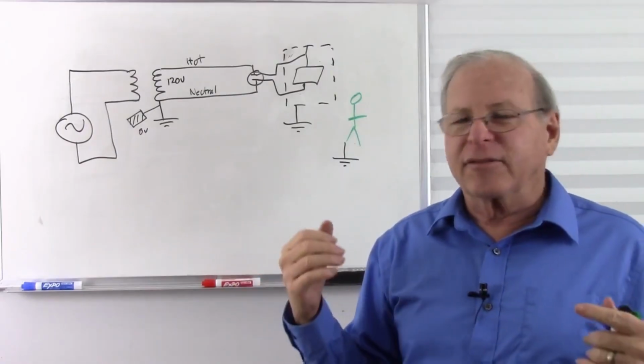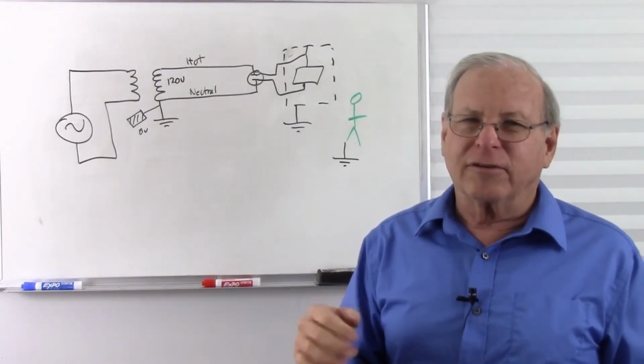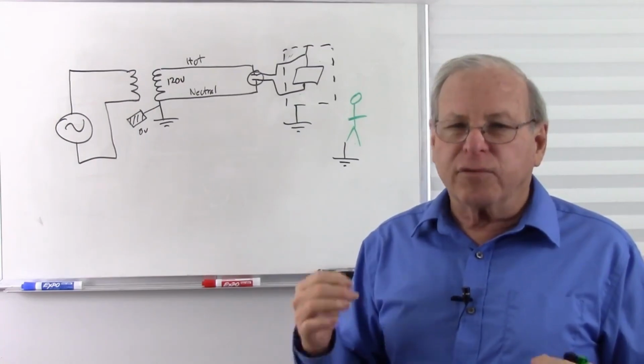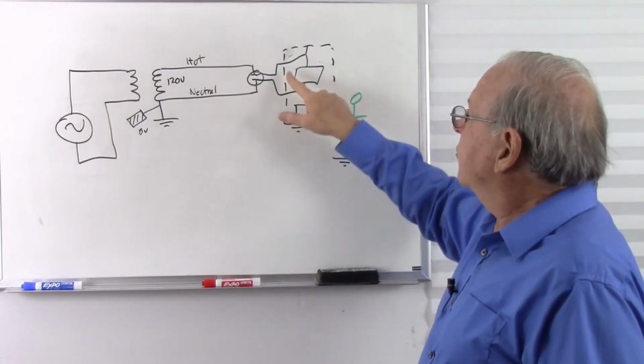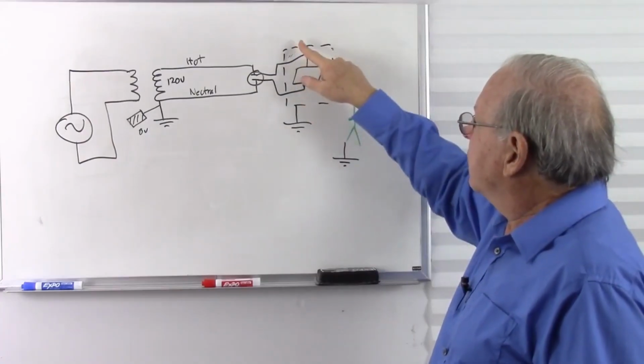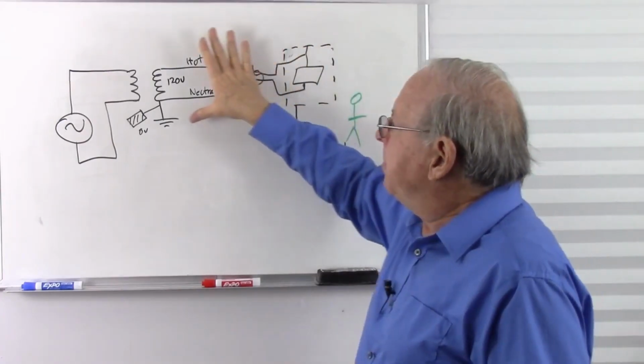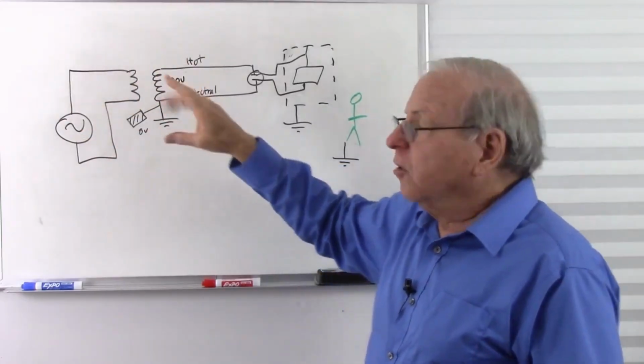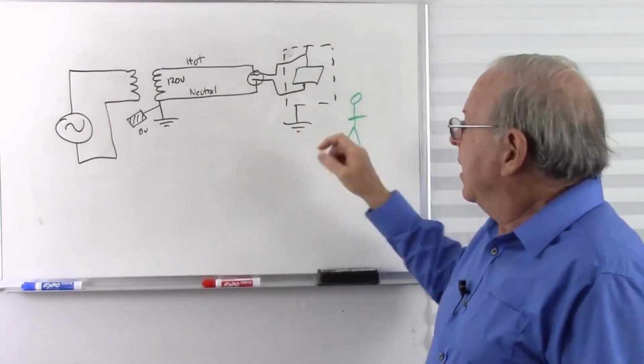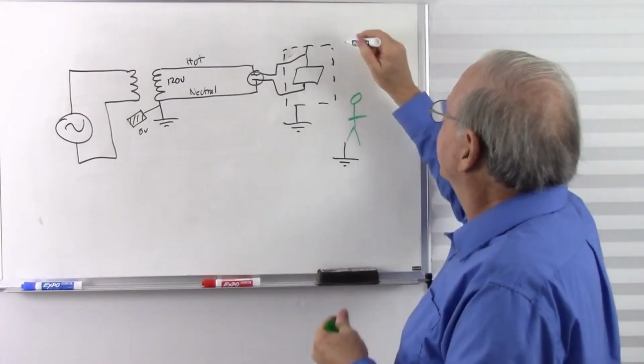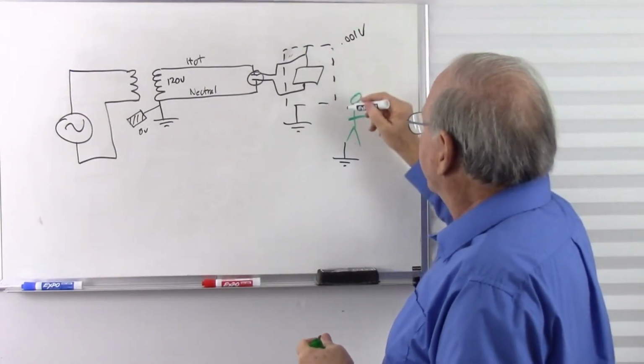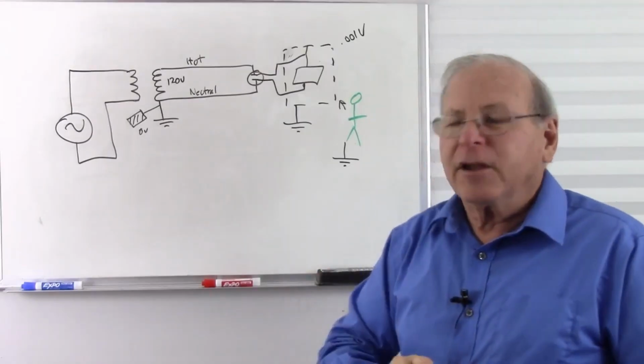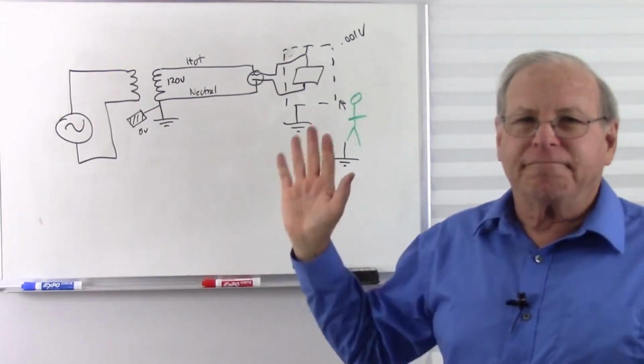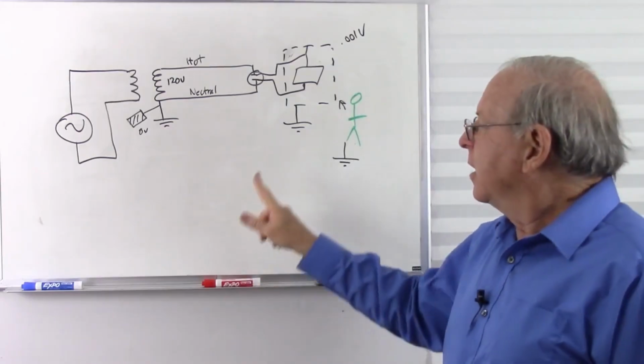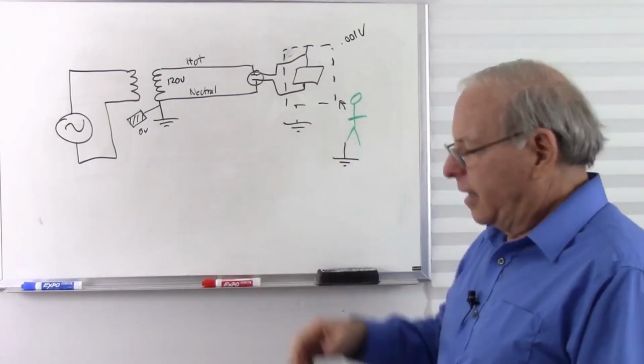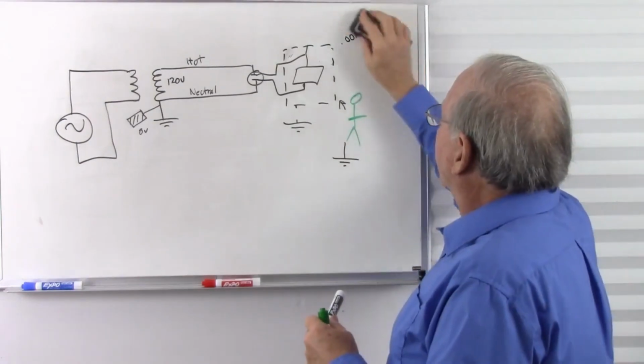Now, you've probably heard that it's not the voltage that kills, it's the current that kills. Yes, it is, but you're not getting current without voltage. The reason this makes things safe is if I do get a connection, this is a very, very low resistance, much lower than the impedance of this whole system over here. So low enough that even though I might get a lot of current, I get very little voltage. So that if I do touch that, I'm safe. So that's all I need to do is ground that, and no problem. Unless something goes wrong with the ground. Now I've got that full 120 volts across me again.